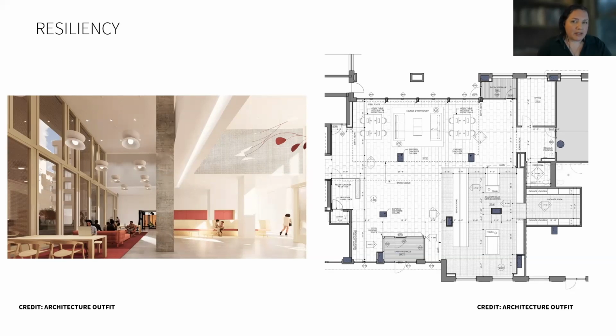However, we are looking at batteries on other projects where the grid is constrained, and the value proposition changes at that point because these batteries can help shave off peak demand if connected to the grid. On this building, through the Buildings of Excellence Award, the team is reviewing the option to add an automatic transfer switch to this emergency generator that would allow additional, although not required, convenience electrical loads to be added to the generator without increasing the size of the generator. So currently this option would add electrical outlets and heating and cooling equipment to the double height entry lobby and lounge at the ground floor, which you can see here.